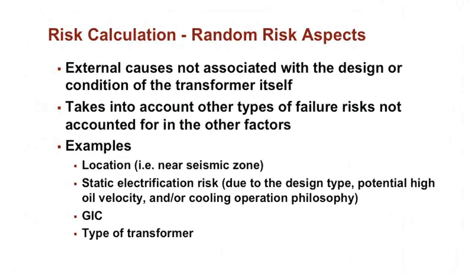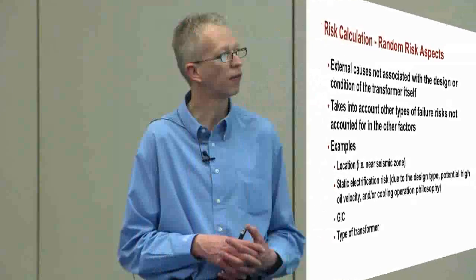Okay, then random risk factors. The other things I was talking about, like a seismic zone. Of course, the west coast of Canada and the United States has much more risk of failure due to earthquake. Generally, if a transformer is designed for seismic, it will usually survive an earthquake. So it's more the transformers that were designed at a time when there weren't regulations requiring seismic design. Then there's static electrification. This is a problem that came about in the 80s and 90s, where the velocity of the oil going through the windings could actually cause a dielectric failure. That is generally for certain vintages of transformers.